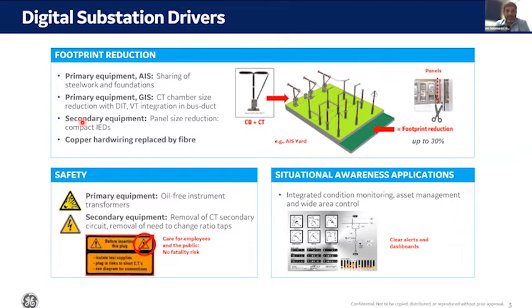The second aspect is safety. It's always a challenge to work in a live substation for any kind of testing or maintenance. When it comes to the digital substation, this has become kind of plug-and-play. We can do testing remotely with no need to carry big testing equipment or manpower to the equipment being tested. Testing time is reduced and it is safer because we are no longer dealing with AC current and AC voltage at the control cubicle side.